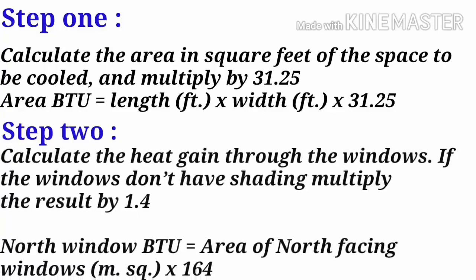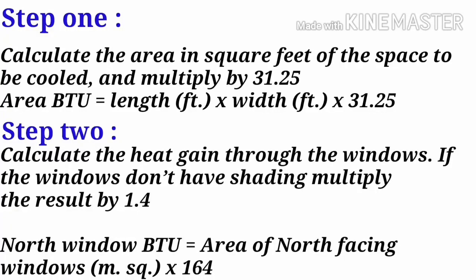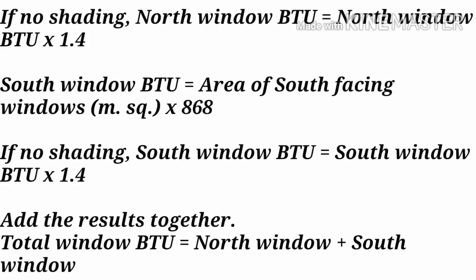Step 2: Calculate the heat gain through the windows. If the windows don't have shading, multiply the result by 1.4. North Window (BTU) equals area of north-facing windows in square meters multiplied by 164. If no shading: North Window (BTU) equals North Window (BTU) multiplied by 1.4. Similarly for south-facing windows — if no shading, South Window (BTU) equals South Window (BTU) multiplied by 1.4. Add the results together: Total Window (BTU) equals North Window plus South Window.